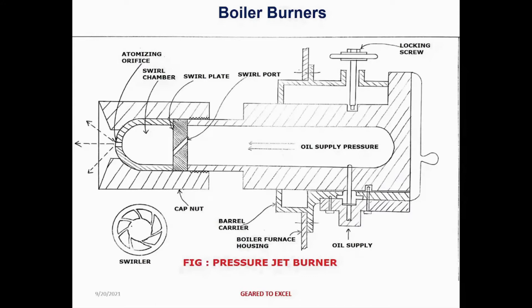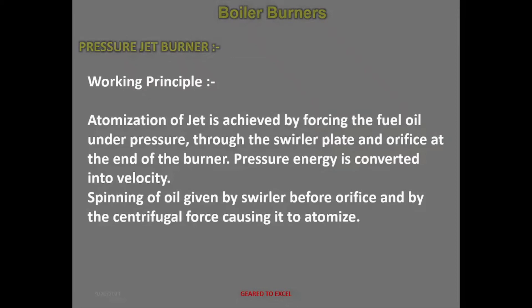Working principle of the pressure jet burner: atomization of the fuel jet is achieved by forcing the fuel oil under pressure through the swirler plate and orifice at the end of the burner. Pressure energy is converted into velocity; spinning of the oil is given by the swirler before the orifice, and by centrifugal force, causing it to atomize.